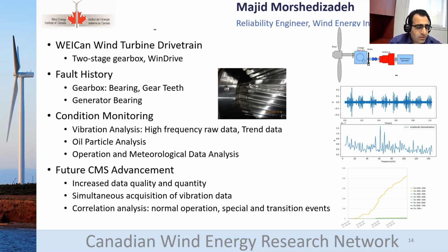We have had our share of failures, or maybe more than our fair share of failures, in our drivetrain components, mostly in the gearbox. We have had failures in the bearings. The axial cracking was the major problem we've had. We have also had some issues with gear teeth. As you can see in this picture, a very clean, beautiful cut in one gear tooth. And we have also had some issues with generator bearings.